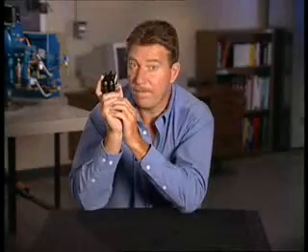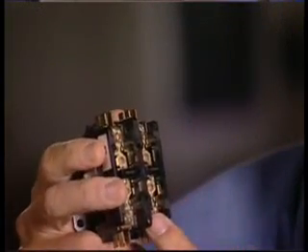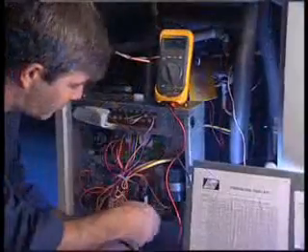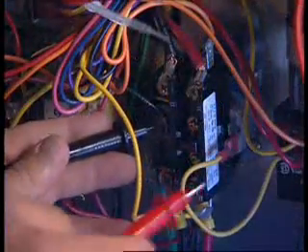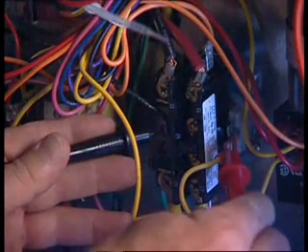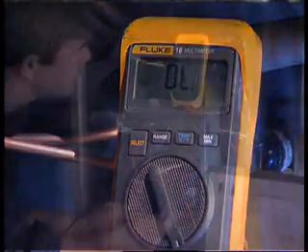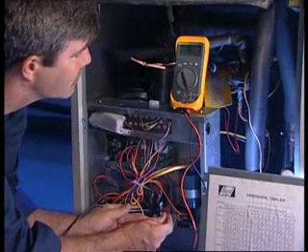When a contactor fails to operate properly, there are three areas that need to be checked: the coil, the contacts, and the mechanical linkage. The failure of any of these parts will cause the contactor to malfunction. The coil of the contactor can be easily checked with an ohm meter. If the resistance of the coil is infinity, the coil is said to be open and must be replaced. Infinite coil resistance indicates that there is a break somewhere in the coil.